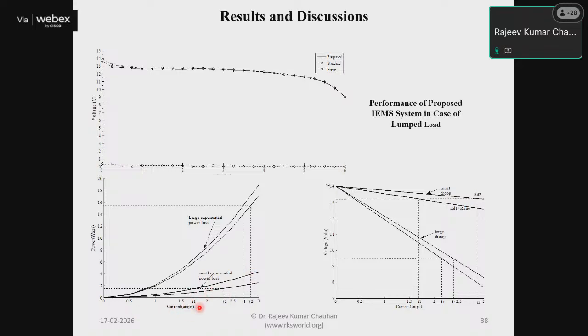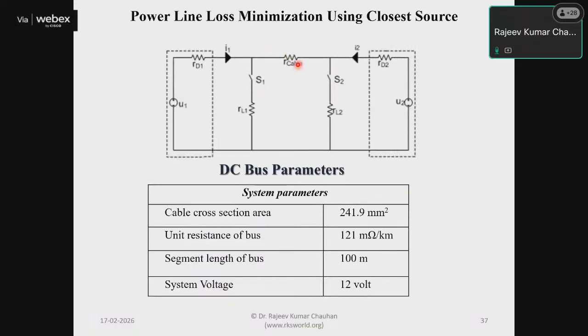We are considering source I1 current and I2 current source. If partial current is supplied by source I1 and I2 is the current source, here the voltage drop will not only cause losses, it will also cause a voltage drop, because if we consider this source is, say, 10 km far, and this other source is just close to the load, 1 or 2 km, the cable resistance will cause this voltage drop.